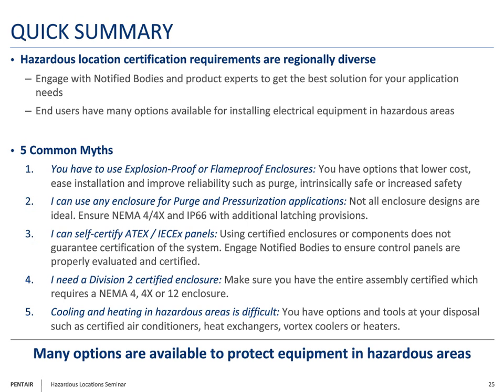When you're looking at purge applications, really look at the enclosure design and make sure you're adding the right latching provisions, so that you're able to hold purge and you won't have a lot of air leakage out of the enclosure. Again, when you're looking at ATEX and IECEx control panels, engage with a notified body if you're going to do a design for ATEX Zone 1 or Zone 2. We just think that's a best practice, and it's a requirement for ATEX Zone 0, 1 and IECEx Zone 0, 1, and 2. For Division 2 applications, if you're using certified components in your system, you just need a NEMA 4, 4X, or 12 enclosure, nothing more than that.